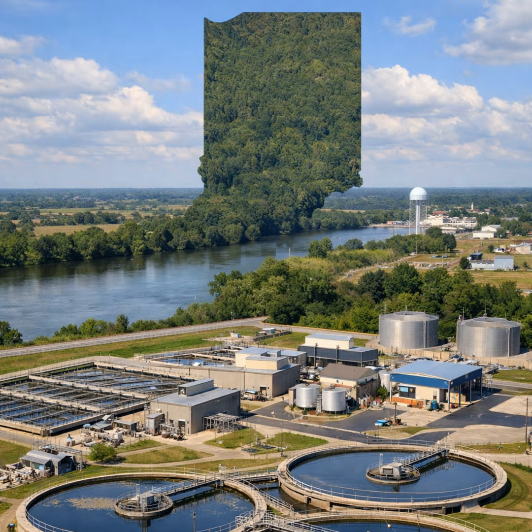What is MCRT and SRT? MCRT, or mean cell residence time, is an expression of the average time, usually days, that a microorganism will spend in the activated sludge process. MCRT is the mass of the bacteria in the system. And a desired MCRT for a conventional plant is 4 to 15 days. So the mean cell residence time is how long the mass of bacteria is held in a system.